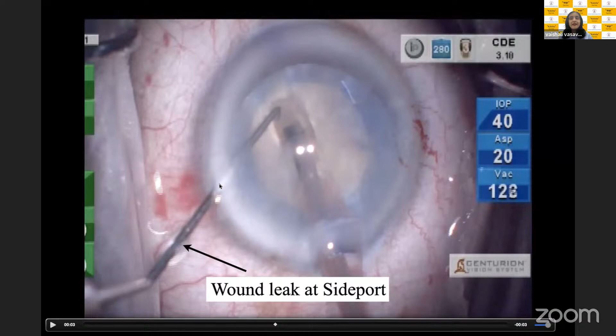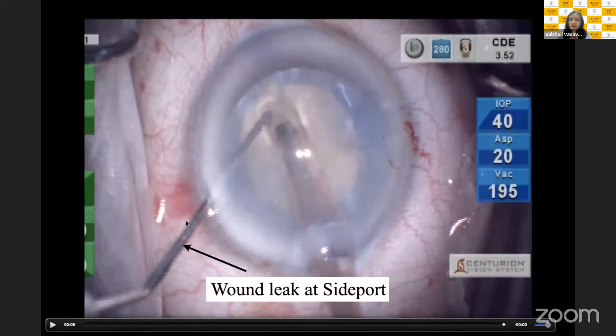Now typically the side port knife that most of us use is the stab knife, the yellow stab knife. There you don't know exactly what the size is, because the bevel, if you see, is tapering and then it becomes broad. So even if it's a 1 millimeter side port, the chopper diameter is much less, so there's a lot of leakage happening. Therefore, in such cases, either you make a smaller incision or you raise your bottle height so that you can compensate for that leakage.